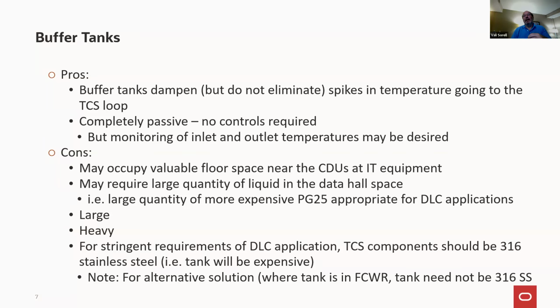Okay, so anyway, the cost does add up. The liquid is pretty expensive, and you may need to store quite a bit. And now you have to apportion some space for the tank, for the liquid, and you've taken on extra cost. They're large, they're heavy, and because the TCS loop has such strict requirements, because the liquid actually doesn't just go through the pipe, it goes through very narrow, almost millimeter type, micron dimension passages as it goes through the cold plate at the GPU level.